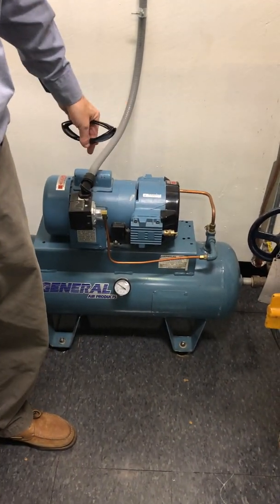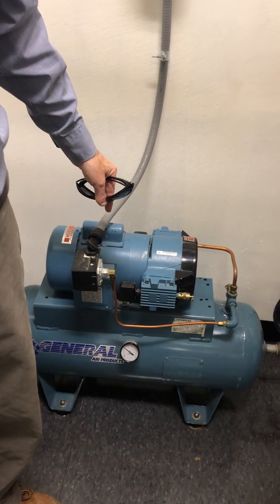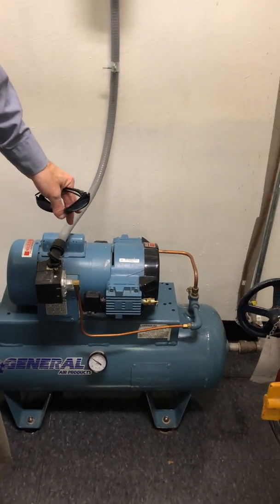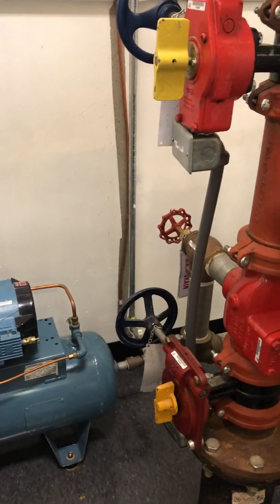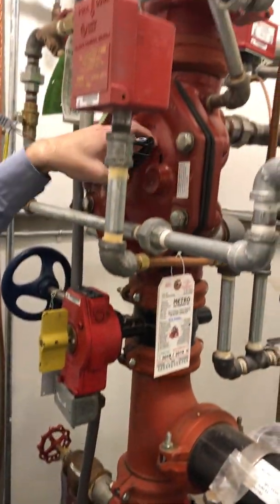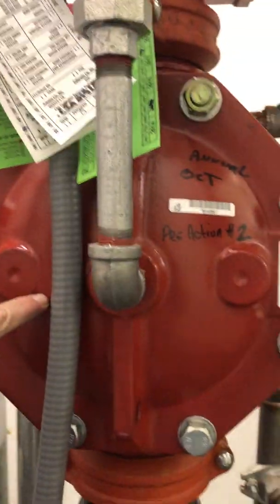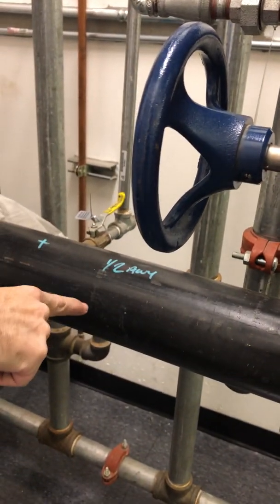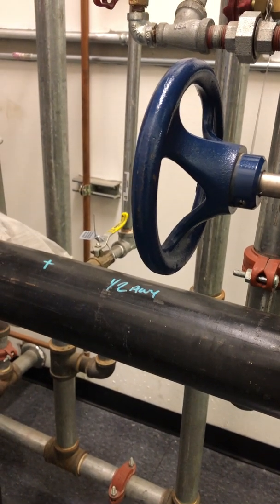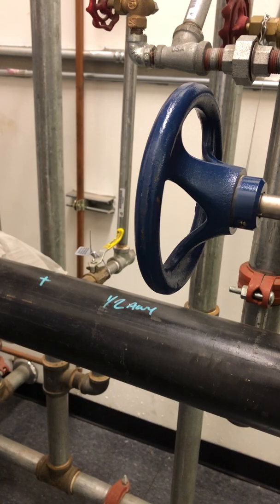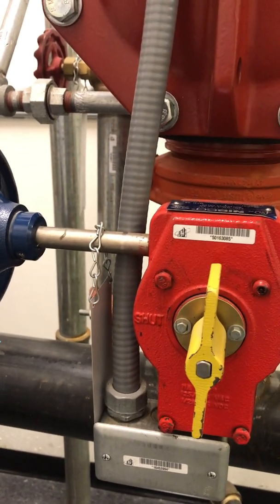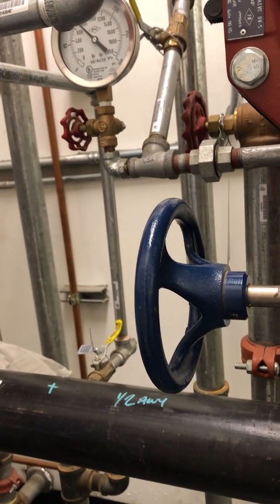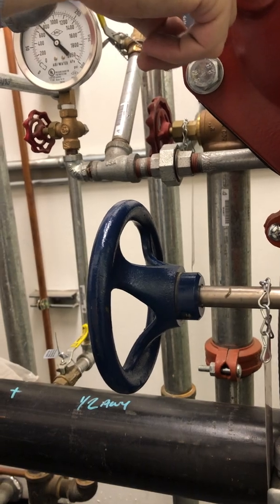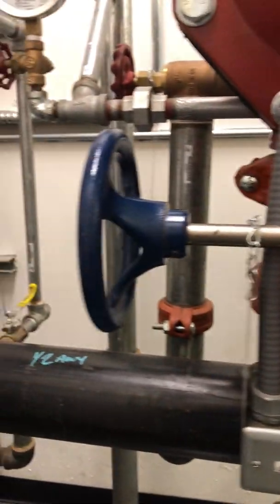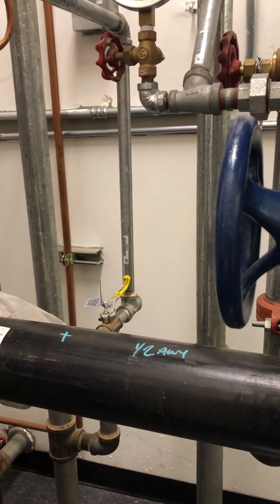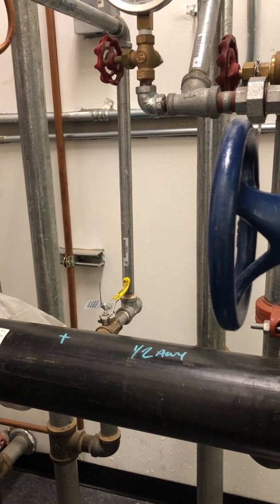As we're on a pre-action system, the pipes in the computer room, the NOC, and the power plant are all charged with compressed air, which this compressor supplies overhead. Backing that up are these huge pneumatic valves which keep the water, which is in this part here, on its own side. So it takes a multiple event to get water into the computer room, the NOC, or the power plant. Gotcha. So you would have to not only have the fusible link and the sprinkler head go off, something else has to happen for this controlled valve to open up. Somebody would have to pull a pull station, or a smoke detector would have to go off, or the pre-action detection would have to go off as a secondary event.